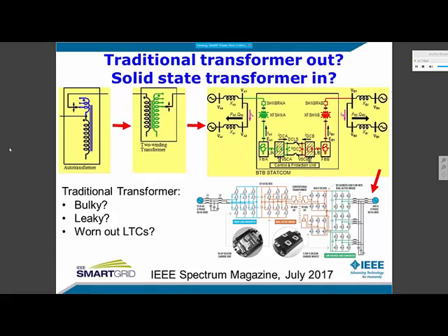Now, my presentation would not be complete if I at least do not briefly mention one other power flow control topology, namely shunt-shunt. In comparison, the autotransformer is a shunt-series topology, where the shunt winding is a high voltage winding and low current rated, and the series winding is a low voltage winding with high current rating. Therefore, the overall power rating of these windings is a small number.